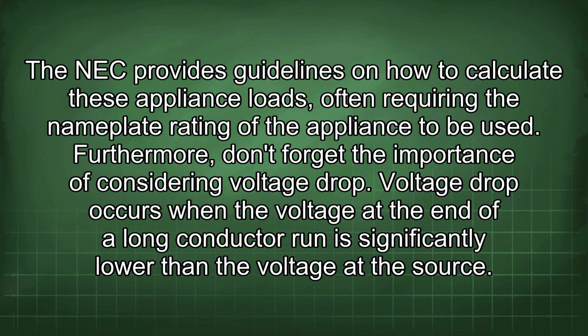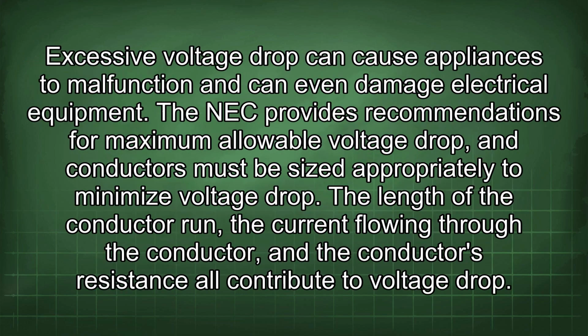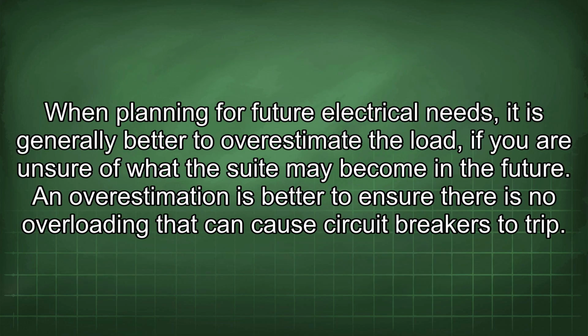Voltage drop occurs when the voltage at the end of a long conductor run is significantly lower than the voltage at the source. Excessive voltage drop can cause appliances to malfunction and can even damage electrical equipment. The NEC provides recommendations for maximum allowable voltage drop, and conductors must be sized appropriately to minimize voltage drop. The length of the conductor run, the current flowing through the conductor, and the conductor's resistance all contribute to voltage drop. When planning for future electrical needs, it is generally better to overestimate the load if you are unsure of what the suite may become in the future. An overestimation is better to ensure there is no overloading that can cause circuit breakers to trip.